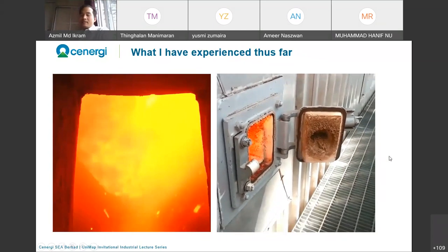Basically, to avoid this, coal power plants or this coal boiler must be at negative pressure. Whenever you open this peephole, air will be sucked in. The reason for negative pressure is very simple. You don't want to make the boiler explode. Number two, you want all the flue gas, the hot air, and the flame, the heat that you have generated, to flow through the right parts of the boiler, where the superheater heat exchanger is, the region where you exchange heat with steam.